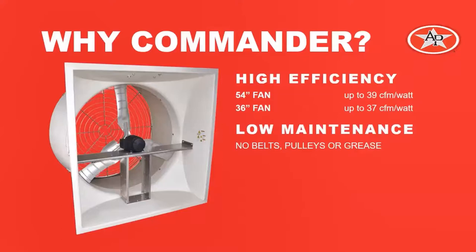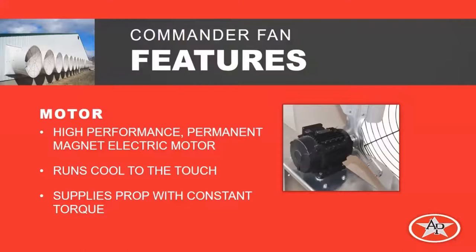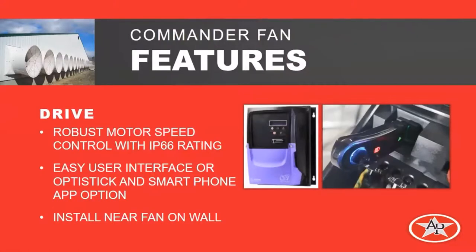Another great advantage is its high efficiency. With all the Commander fans, their efficiency increases as they slow down. The 54-inch fan has an efficiency of up to 39 CFM per watt, and the 36-inch fan up to 37 CFM per watt. The last advantage is very low maintenance, since it's a direct-drive fan — there are no belts to tighten, no pulleys to maintain, and no open arms to grease. The motor is a high-performance permanent magnet electric motor that runs cool to the touch and supplies a constant torque to the prop. The drive, located near the fan on the wall, is a robust control with an IP66 rating. The main power and the control signal from the main ventilation control come into this drive, and it operates the fan at that speed.